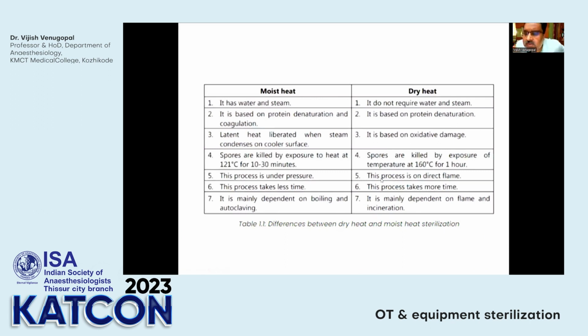So what is the difference between moist heat and dry heat? Moist heat is the autoclave one, and dry heat is the hot air oven. In moist heat, we have water and steam, whereas in dry heat there is no water and steam. It is just flame and incineration. The technique is based on protein denaturation and coagulation in moist heat, whereas it is just protein denaturation in dry heat. Another important thing is that the process in moist heat is under pressure. So suppose the steam is at 121 degrees, you will have to sterilize for around 15 to 20 minutes. Whereas if you increase the temperature to 136 degrees, you can get the sterilization effect in 5 minutes.